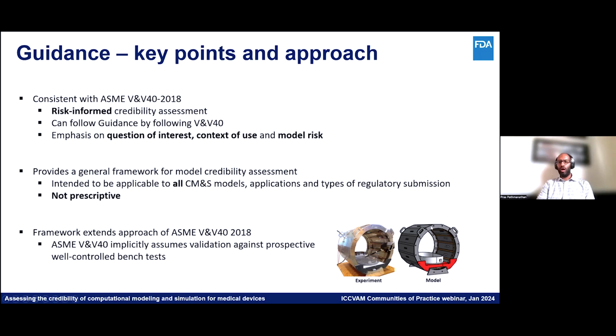Basically the question being assessed here is, when people have metallic implants and then need an MR scan for maybe some unrelated condition, those implants can absorb the radio frequency energy emitted by the scanner and possibly heat up dangerously. So to understand if it's safe for a person with a metallic implant to undergo MR imaging, computational modeling is often used to assess the possibility of dangerous thermal damage.